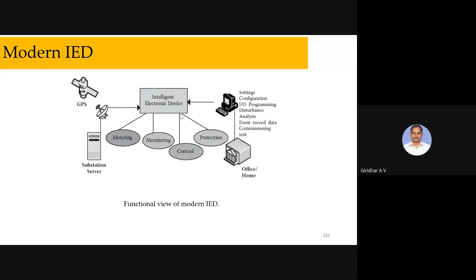the protection feature, and it even has PMU features, phasor measurement unit features, through GPS time synchronization also. In that way, these IEDs are nowadays being used in the expansion of substations, where at higher voltage levels also these IEDs are preferred very well.